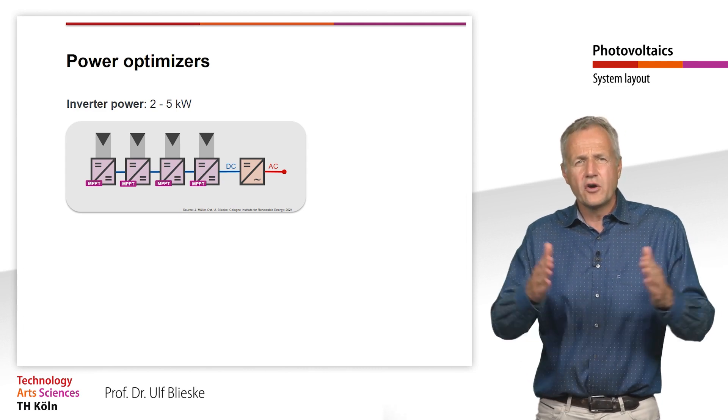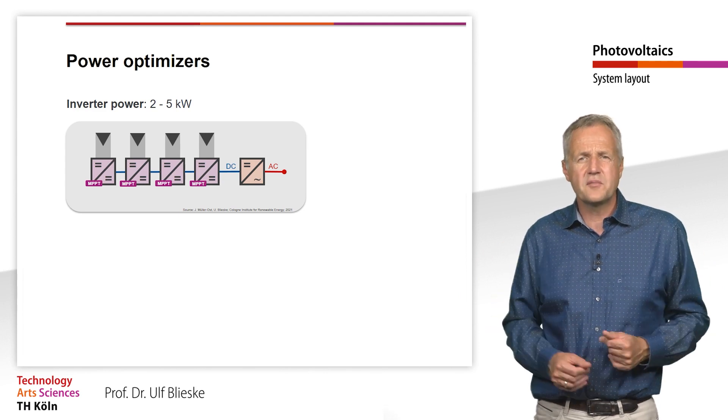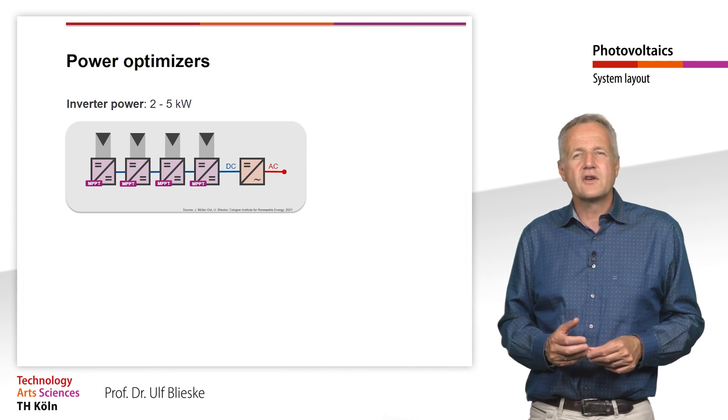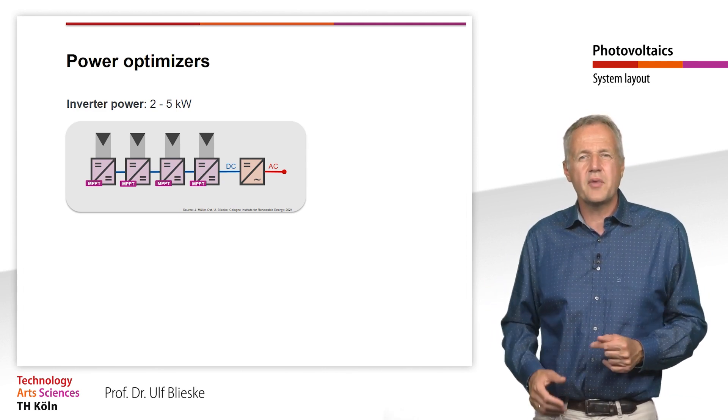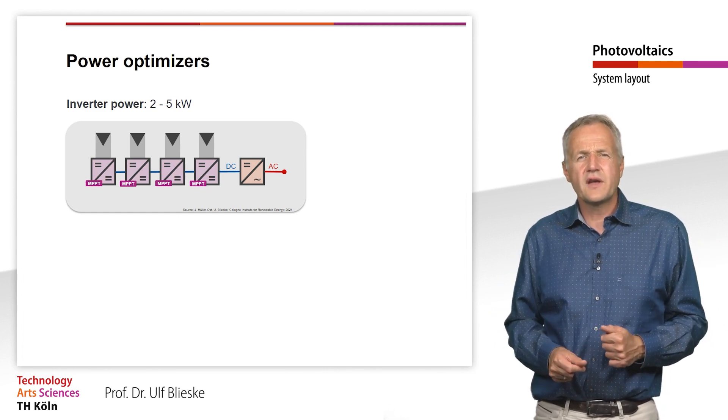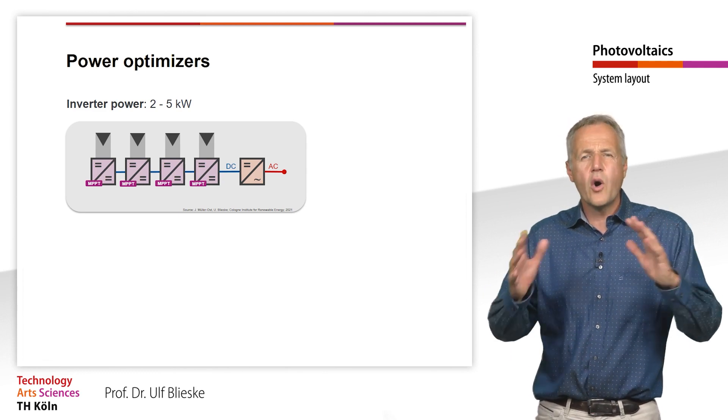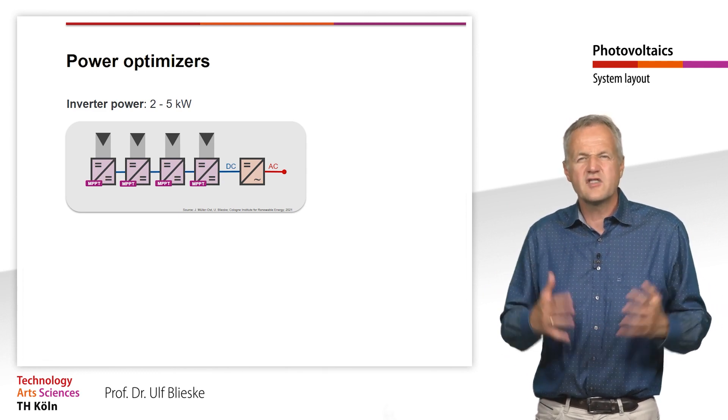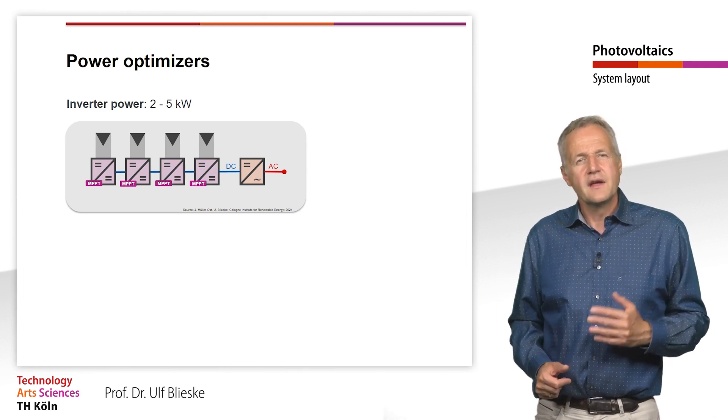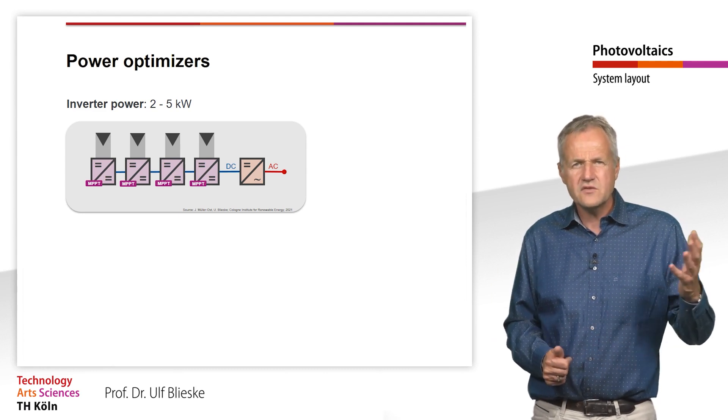The series connection of the modules is also one of the main advantages of the power optimizers concept compared to module inverters. With module inverters, the modules are connected in parallel, leading to higher power losses in the cable. The voltage of a system with string inverters are usually higher than 230V, leading to lower ohmic losses in the cables. Furthermore, power losses due to DC current are lower than those to AC current at comparable voltage level.